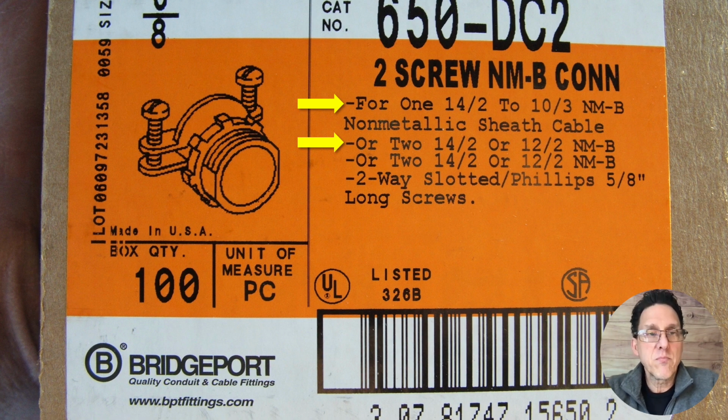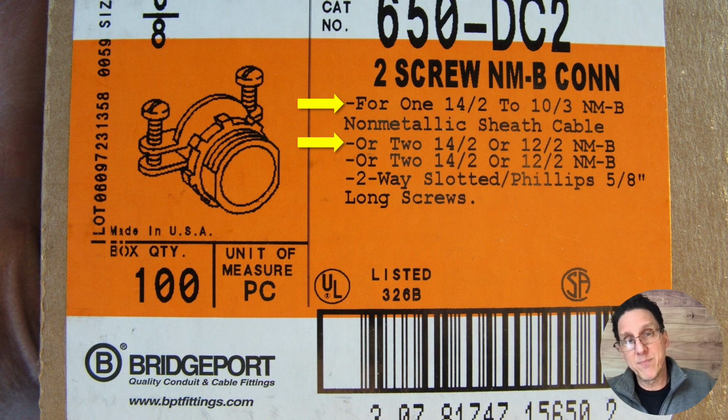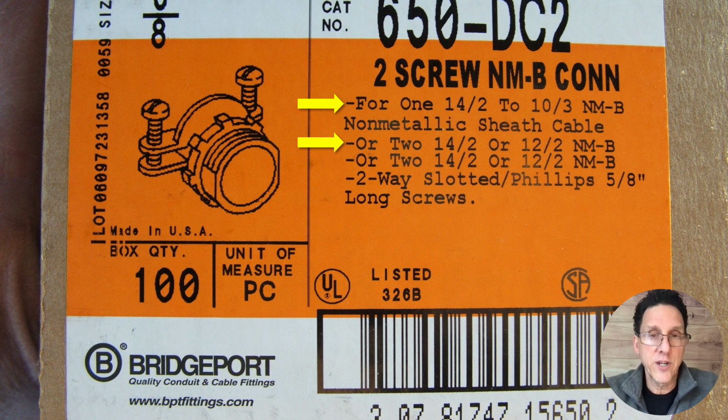Now, what if I decide, well, can I use this connector with UF cable, right? UF cable is non-metallic. It's not a metal cable. Can I use this with UF cable? Doesn't say on the carton that it's okay for UF cable, right? Let's say you run some UF outside, but it comes inside to the panel board, and you want to put a connector in the bottom of the panel board, and this is the connector you want to use. You want to bring the UF into the bottom of the panel board, or a time clock or something, right? Maybe the UF is going to a post light. Can I use this connector with UF? Well, the box doesn't say anything.